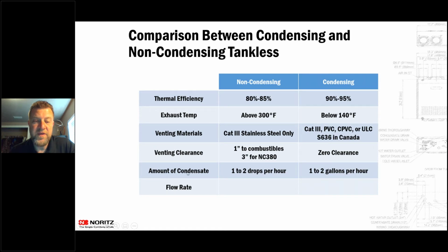So with the amount of condensate that comes out of these units, with the non-condensing units, you might get 1 to 2 drops per hour. With a condensing unit, you could get 1 to 2 gallons per hour of condensate. So that condensate coming out of those units really depends on how many gallons per minute you're running through that unit, to where how much condensate it's going to produce. So if you're only running 1 gallon per minute and you're running at 50 to 70,000 BTUs, it's not going to condense as much as if you were running 5 or 6 gallons per minute through the unit and you're burning at 199,000 BTUs.